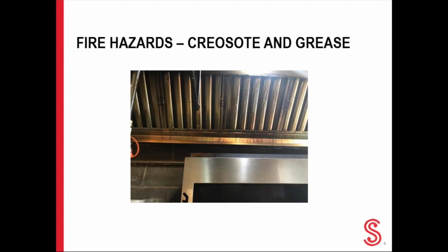Creosote's flash point, which is the lowest temperature at which vapors will ignite when given an ignition source like a spark or a flame, is surprisingly low at only 165 degrees Fahrenheit. All it takes to ignite creosote in hoods, filters, and ductwork is a spark, burning flame, or even a flame that raises the creosote temperature to 165 degrees. Creosote's auto-ignition point, the lowest temperature that the creosote will spontaneously ignite without an external source of ignition, is 451 degrees Fahrenheit.